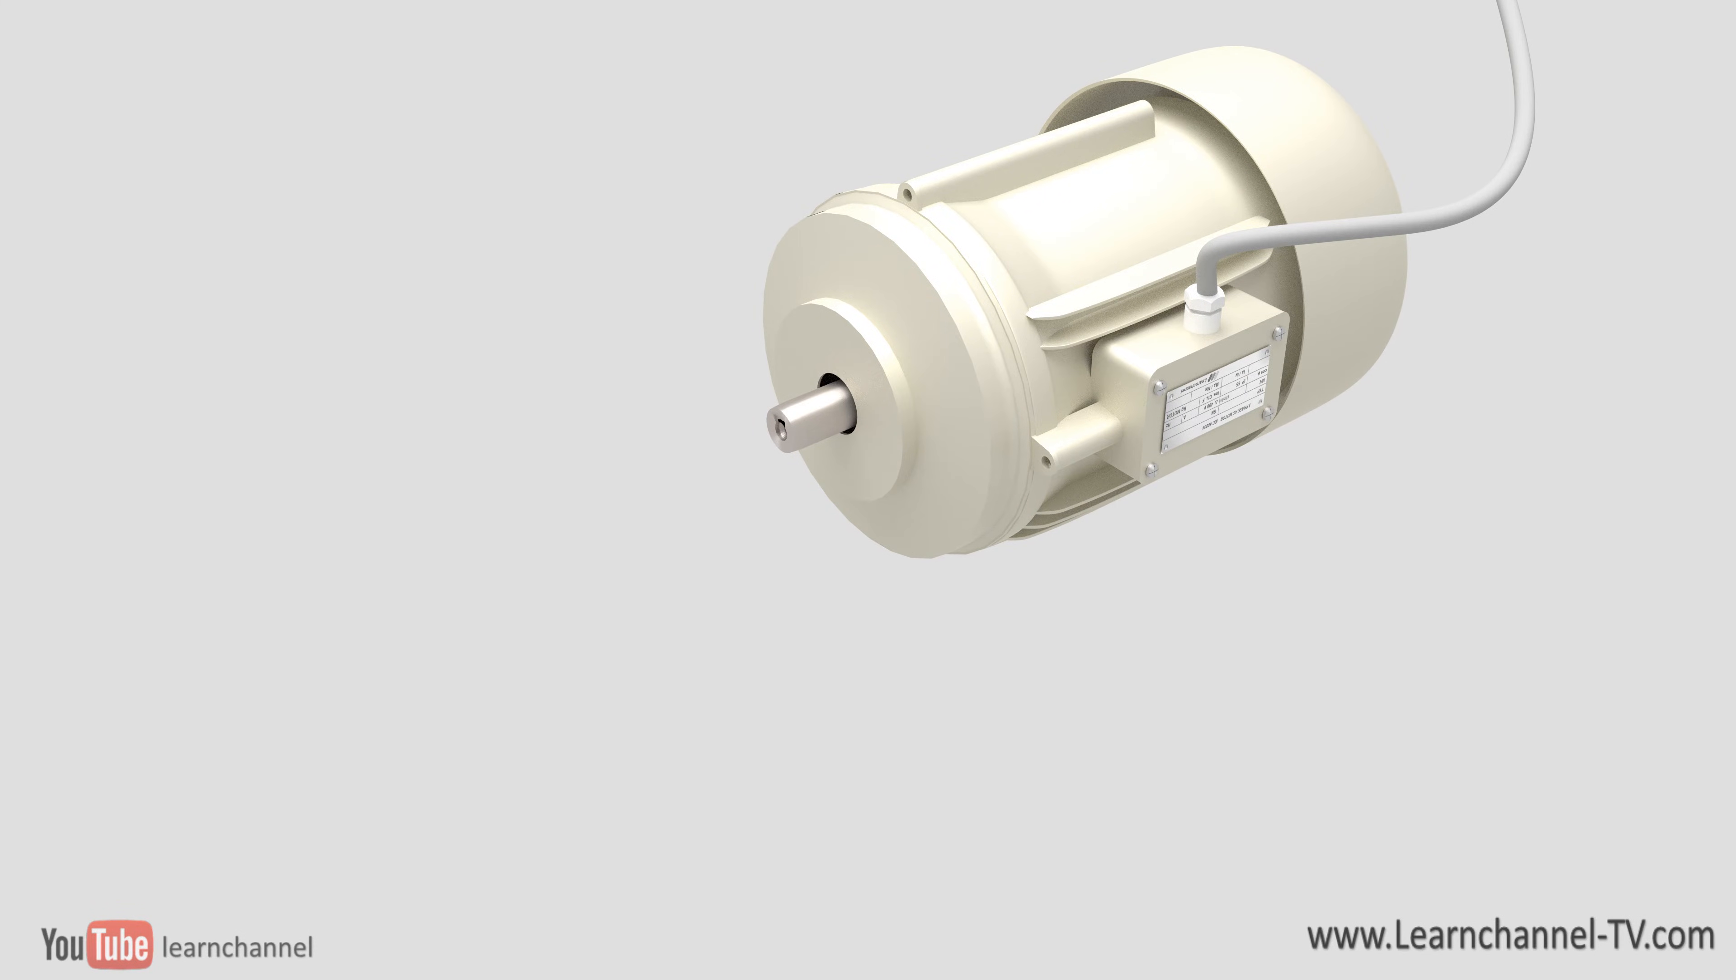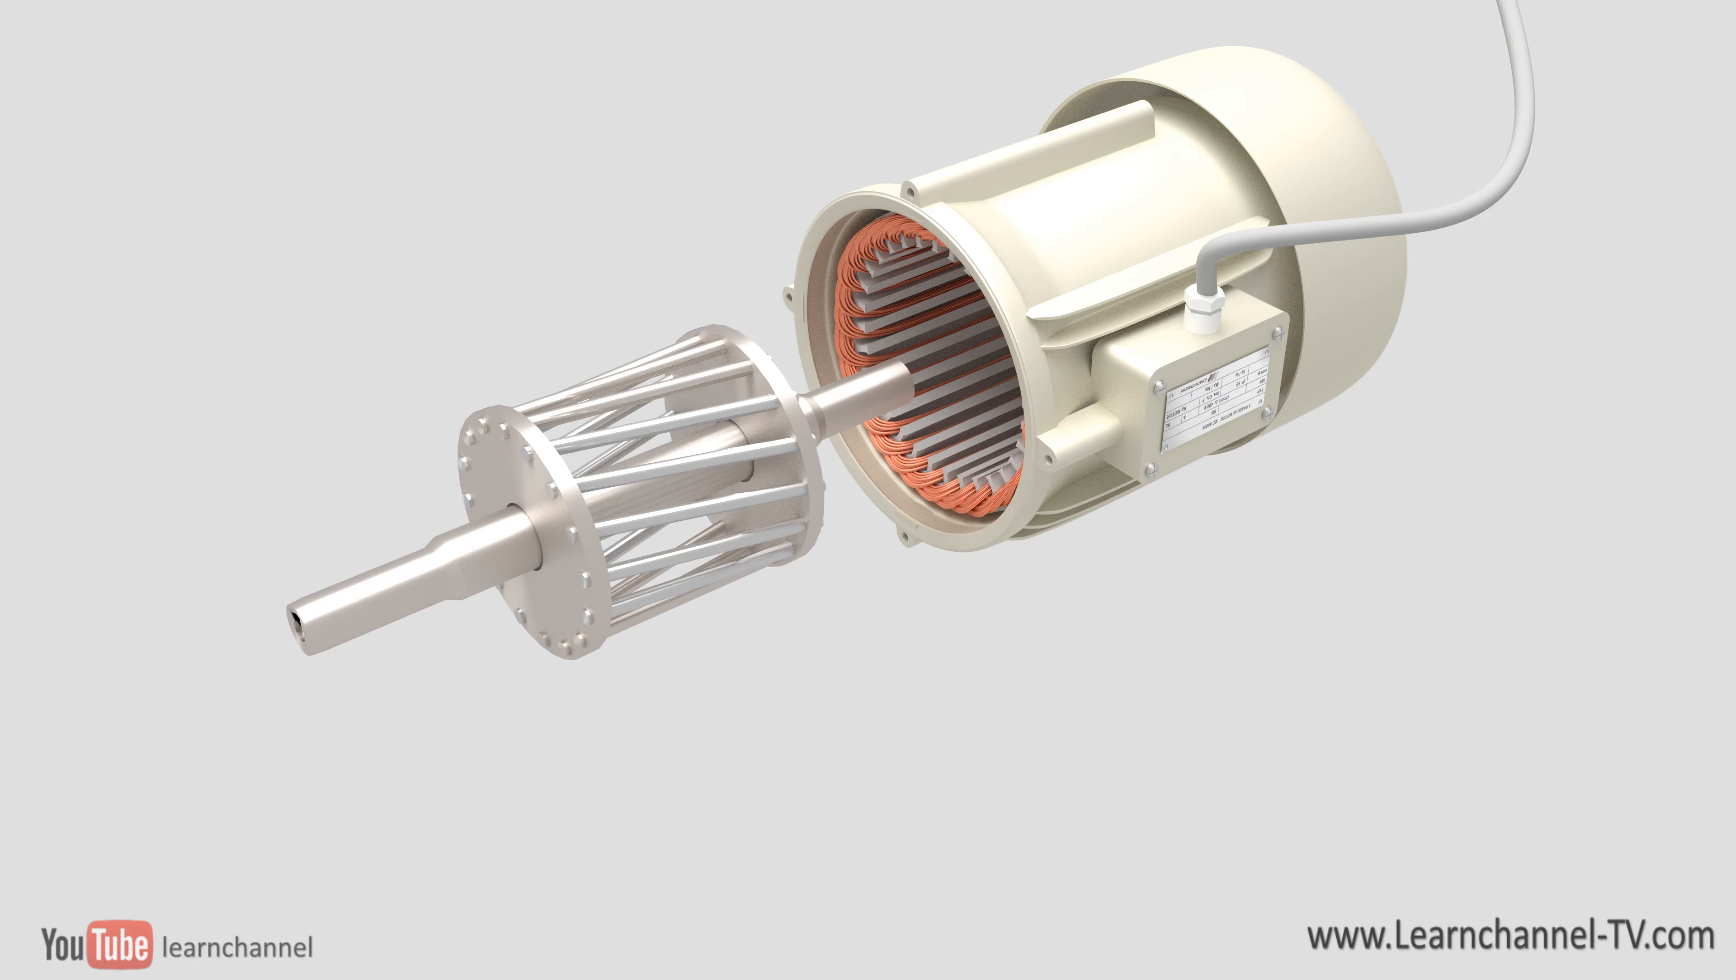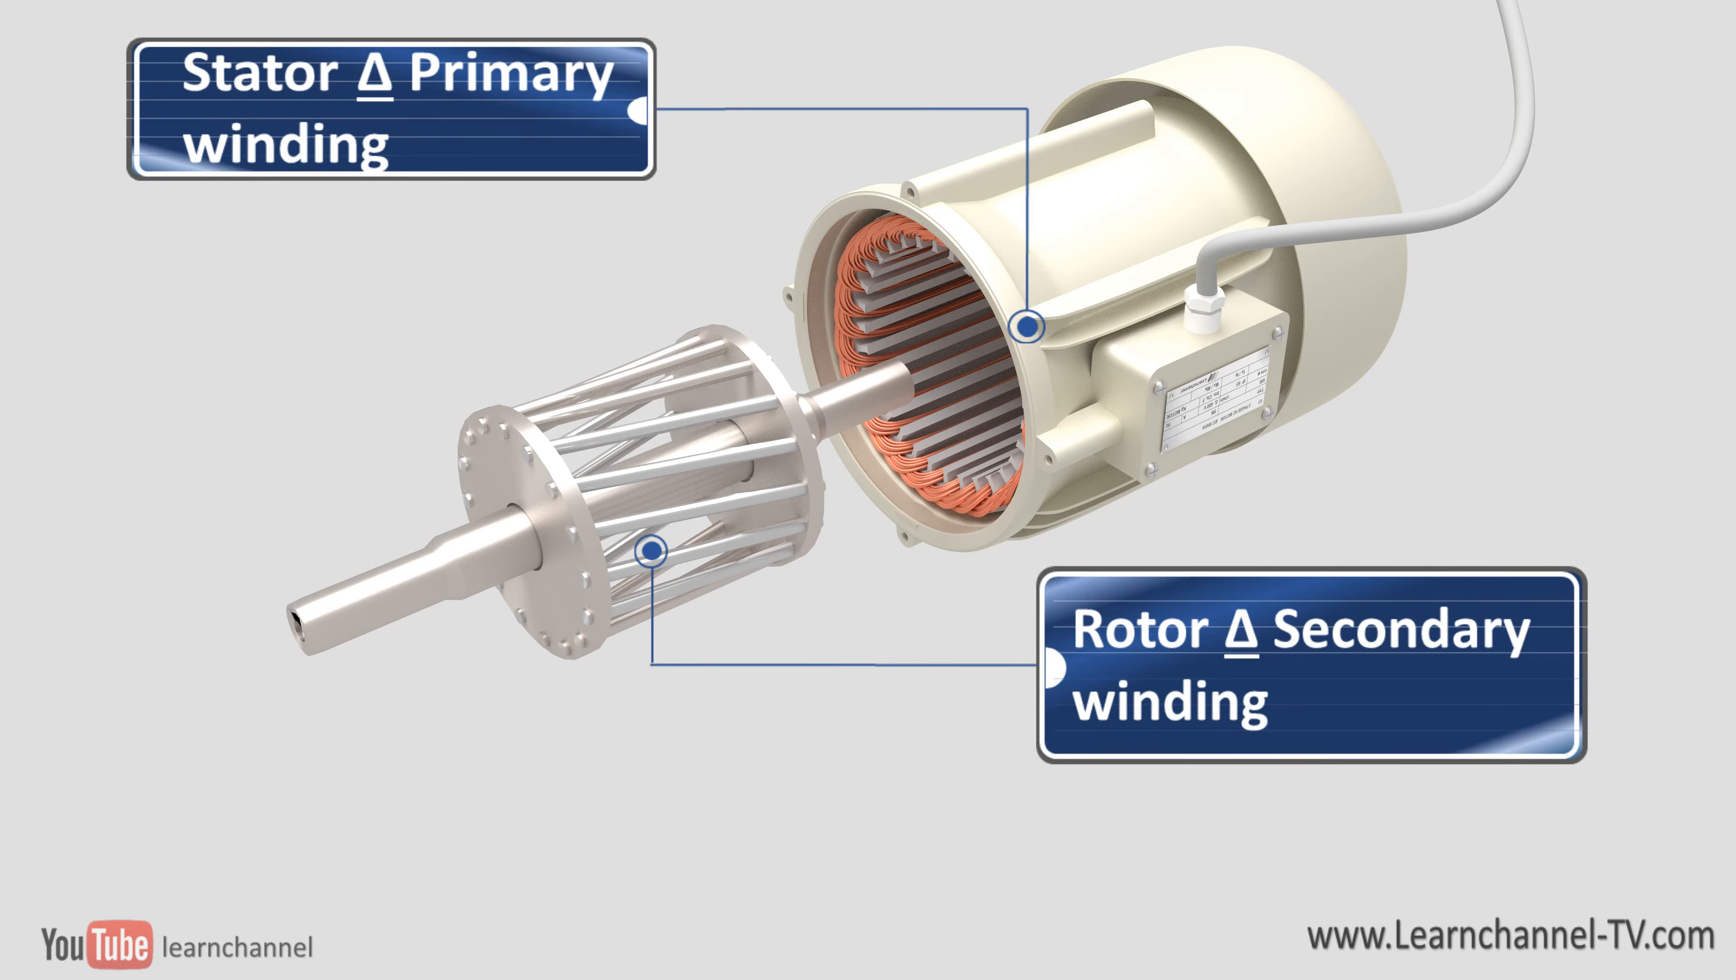from an electrical perspective, the three-phase induction motor can be roughly compared to a transformer. The stator winding represents the primary winding and the rotor the secondary winding. At the moment of starting, this would correspond to a short-circuited transformer.